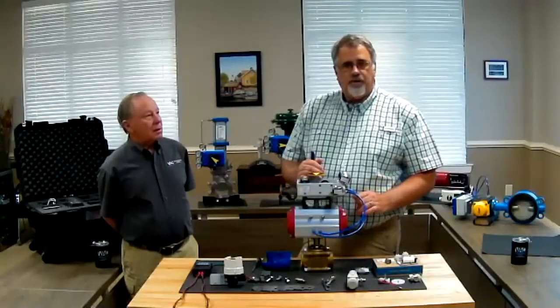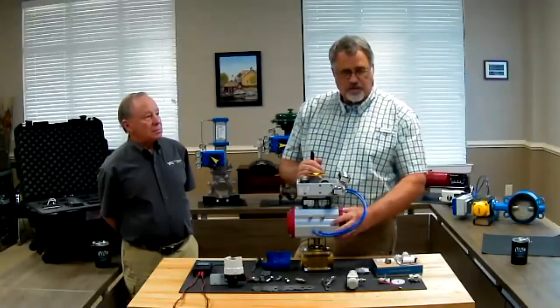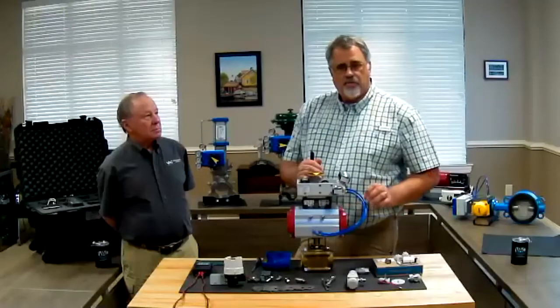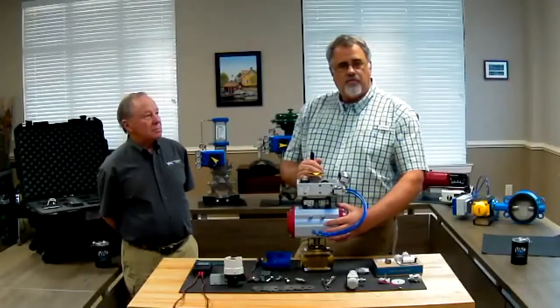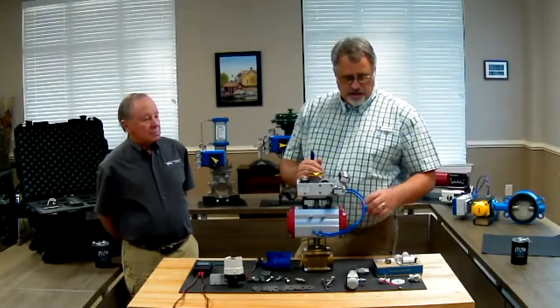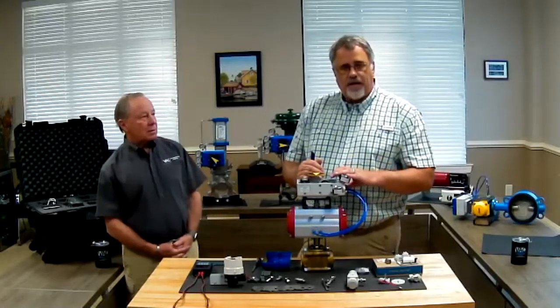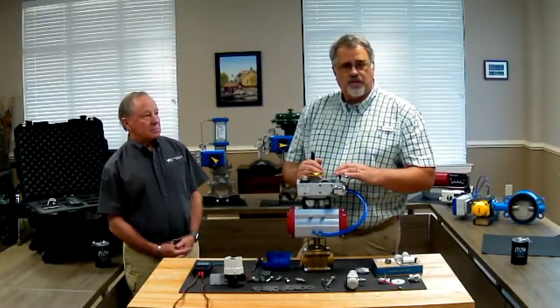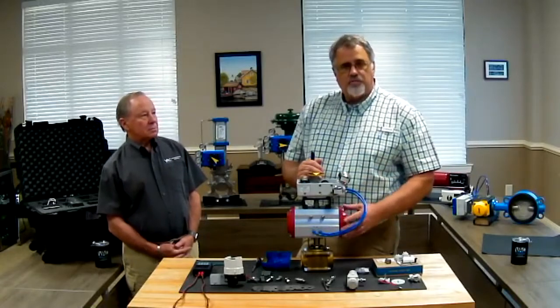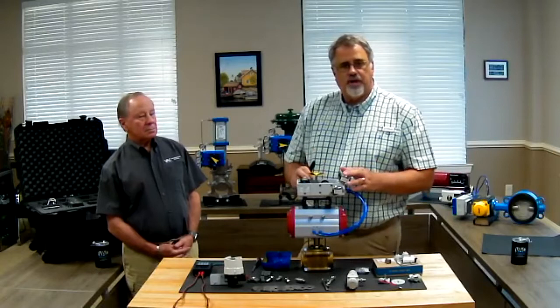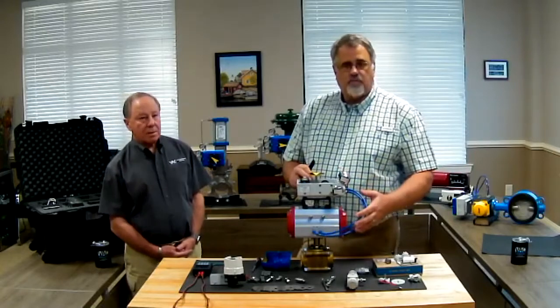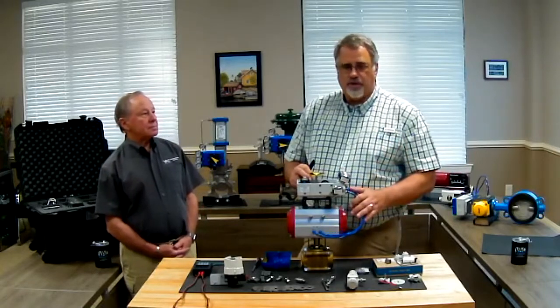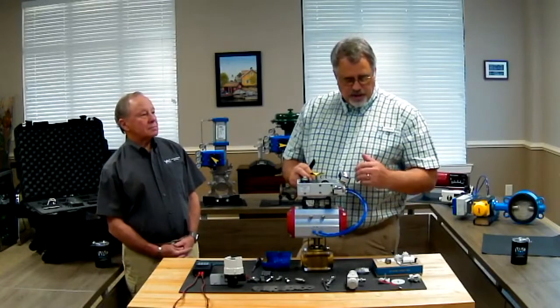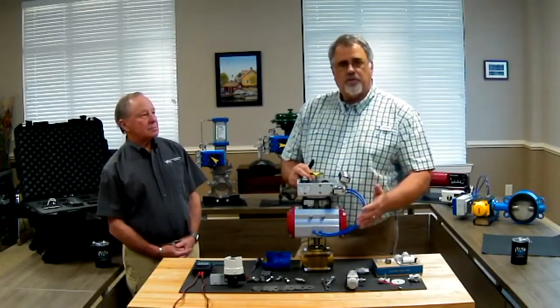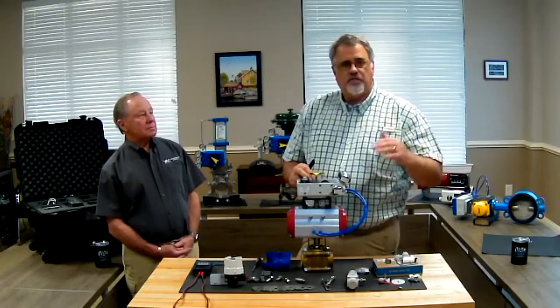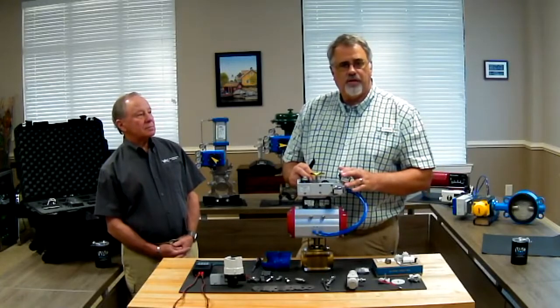Why is that a useful thing? Because by doing this, we're going to actually save the actuator from inhaling the air from the process environment. In this case, we're not changing how the package actually fails on loss of air or loss of signal, but we're making it so the spring side of the actuator only ever sees instrument air. Most plants will find this acceptable. Every once in a while you run across one that thinks it's unacceptable, but if you do this as a standard and you can explain why you do it, you've elevated yourself above what your competitors are doing.